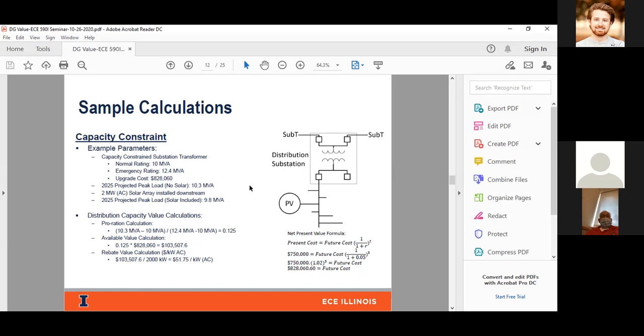So that's an example of a planning criteria that we looked at for a specific substation transformer and where a DG downstream could provide value. We're running a before and after analysis: before with no solar or no DG, and then after with DG, to see if the loading is actually reduced, and that's how we're assigning value to that specific location. A similar analysis would apply to distribution transformers, and you would be able to assign value preemptively across your distribution system.